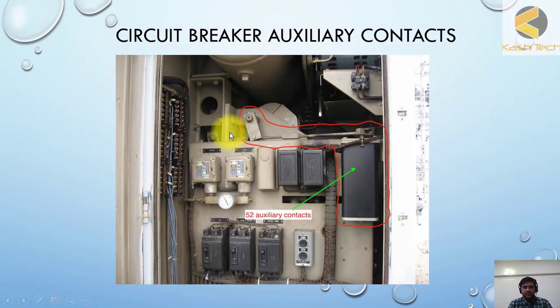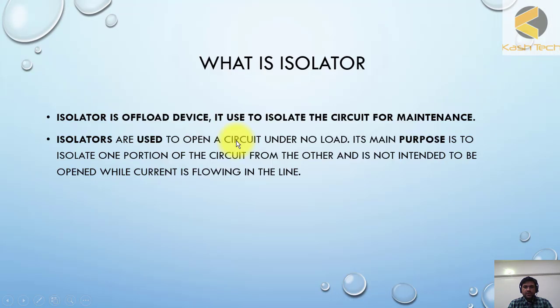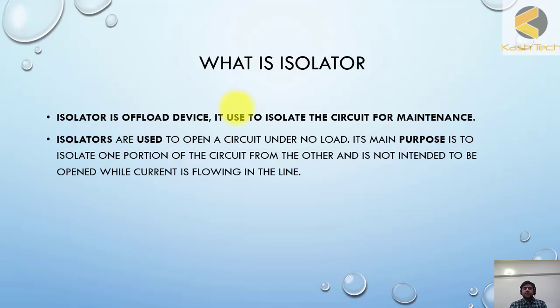Now we move to our next topic: the isolator — another very important equipment used for switching. An isolator is an off-load device used to isolate the circuit for maintenance purposes. Isolators are used to open a circuit under no-load condition. Their main purpose is to isolate one portion of the circuit from another, and they are not intended to be opened while current is flowing in the circuit.